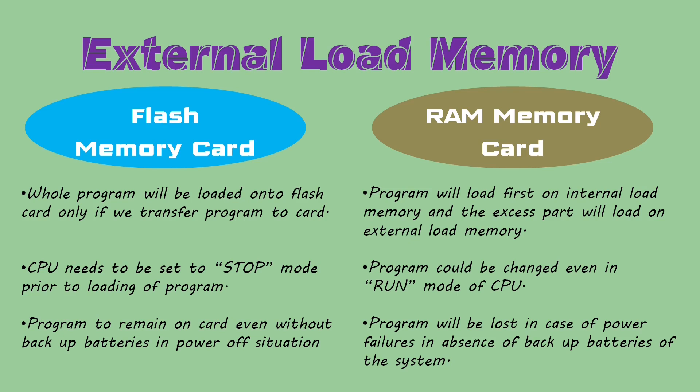In case of a flash memory card, for loading the program onto the flash memory card, the CPU needs to be set to stop mode first. But in case of a RAM memory card, we can change the user program even in run mode.